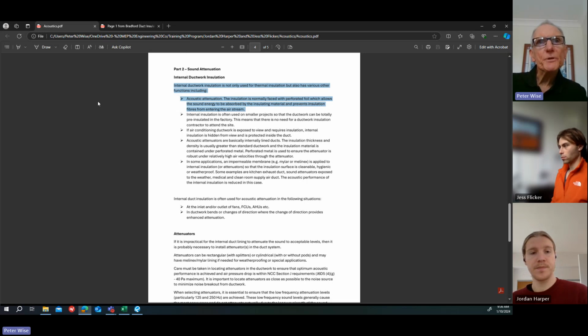So internal ductwork insulation, we have talked about this before, but I'll just go over it again. This is for internal ductwork insulation as opposed to external insulation. The internal insulation has various uses. Firstly, acoustic attenuation. It's normally faced with perforated foil, which allows the sound energy to be absorbed by the insulating material and prevents insulation fibres from entering the airstream. So the perforations allow the sound energy to pass through the foil into the insulation.